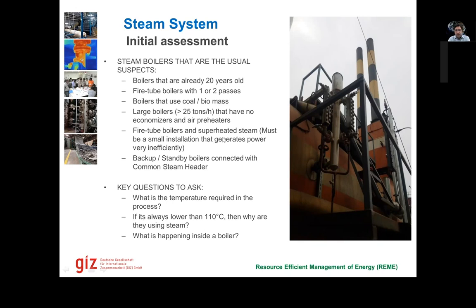So for anything less than 110 degree, 100 degree, if all the processes are there, then we also need to explore this possibility. And then we also need to see what is happening inside the boiler. Is it a single pass boiler? Is it a multi-pass boiler? How is the heat exchange taking place? If it is a solid fuel, what is the size of solid fuel? Is the solid fuel already lost in the bed because it has a lot of fine grains in it, for example? Is the fuel coming out properly burnt or not? Is there any calorific value in the ash that is coming out or not? So these are the things that we also need to have a look at.